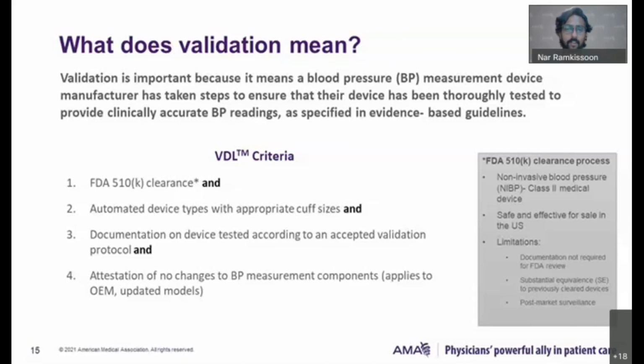Validation means that a manufacturer has taken steps to ensure that their blood pressure devices produce clinically accurate readings. This is why the use of validated devices is specified in clinical guidelines, scientific statements, and most recently, the USPSTF recommendations. Physicians and care teams need to be able to trust that readings are accurate if we're going to move the needle on blood pressure control. Now, validation involves rigorously testing a device according to an internationally accepted validation testing protocol. So essentially a clinical trial where devices need to show a low margin of error to pass, which sounds pretty straightforward. Unfortunately, there are some challenges.